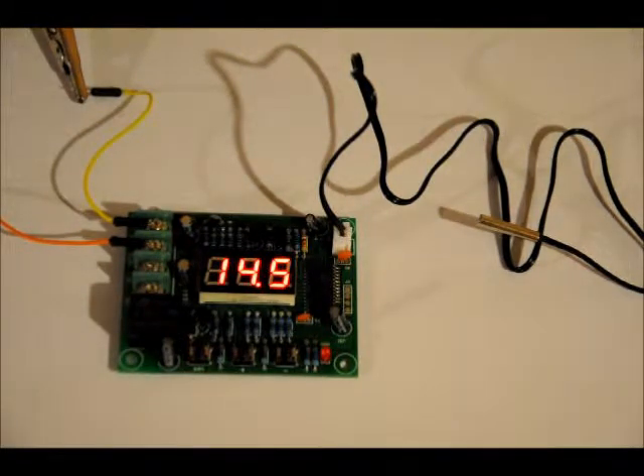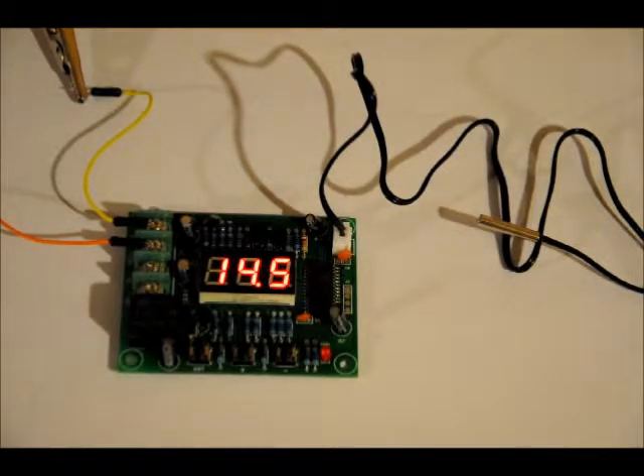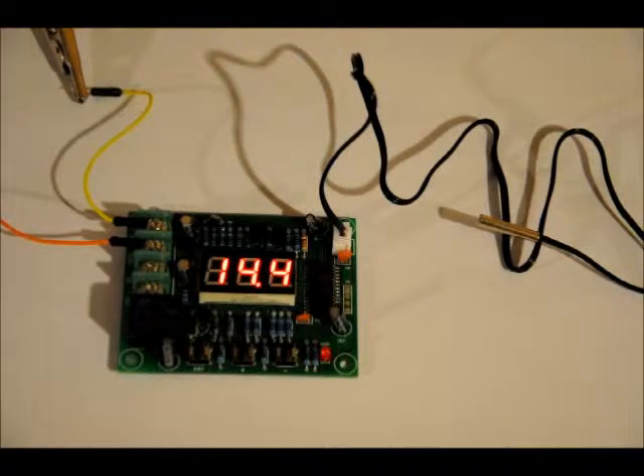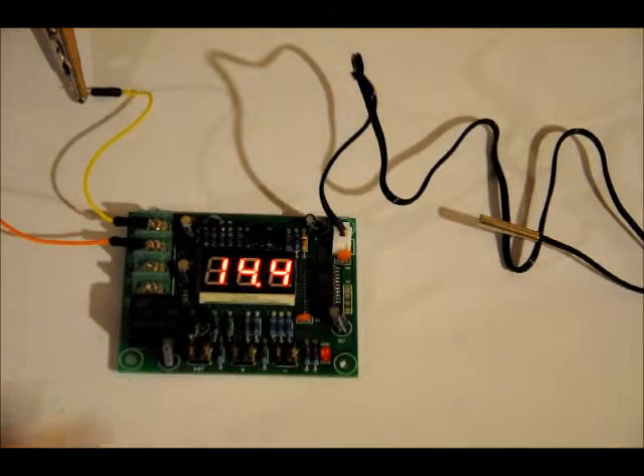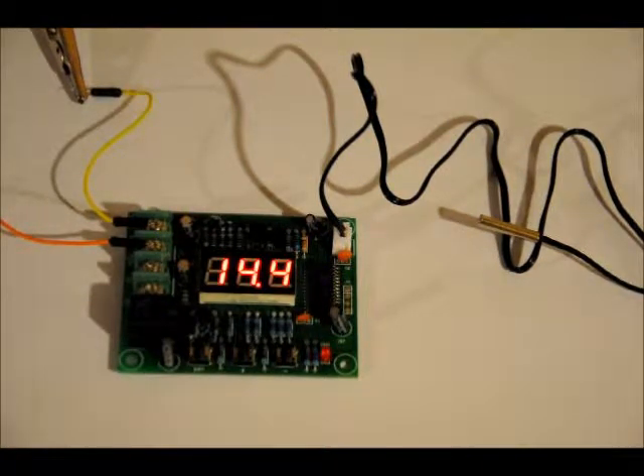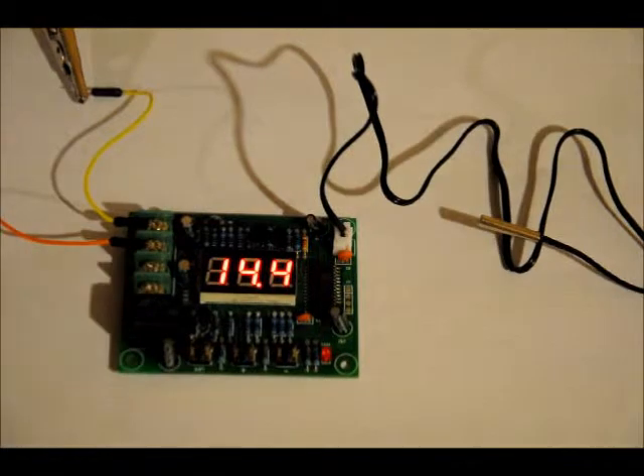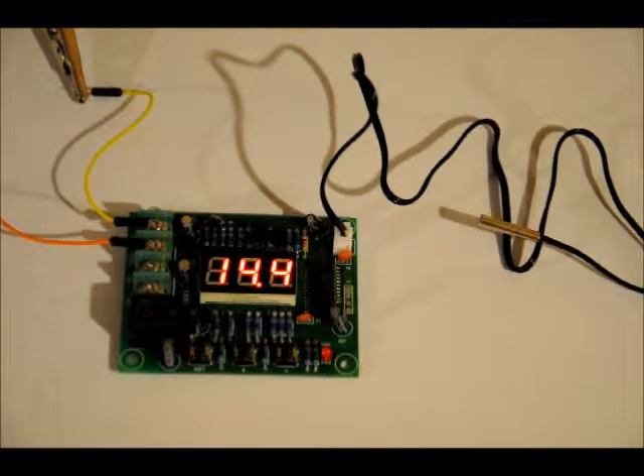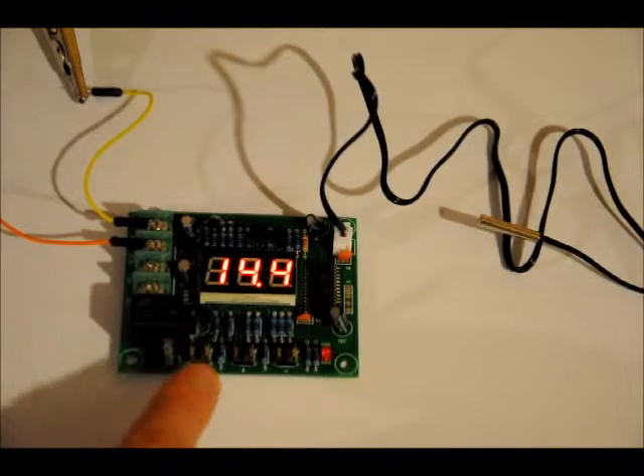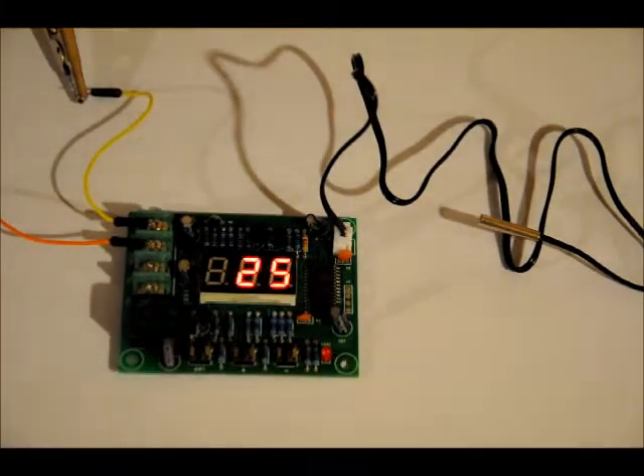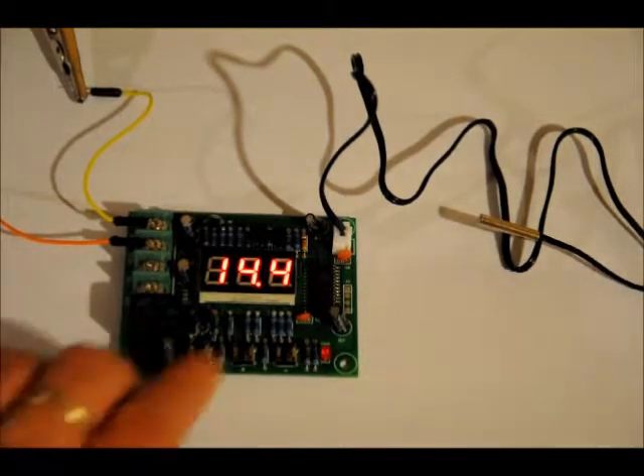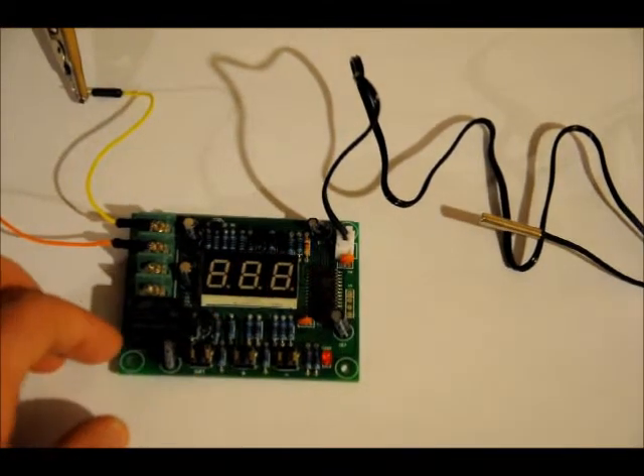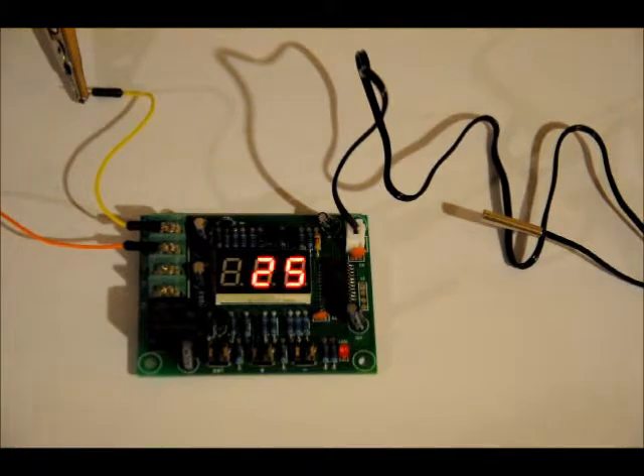So if you find that this temperature is matched up against a very extremely accurate thermometer, and you find that there's a couple degrees difference, you can offset the temperature. So what I'll do is I'll show off the five different programmable aspects of this in just a minute. First of all, I'll show you, you can press the leftmost button, and that will be your reference temperature. If you wait too long, it goes back to the current temperature.